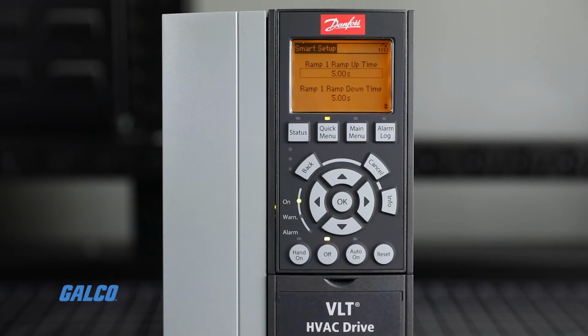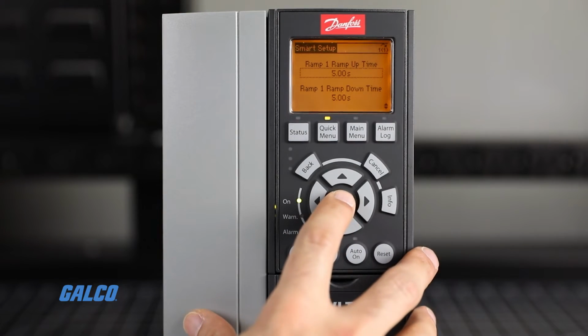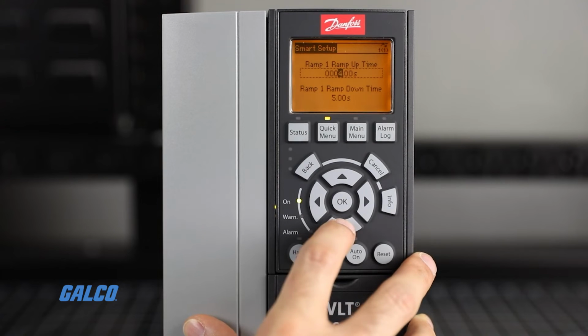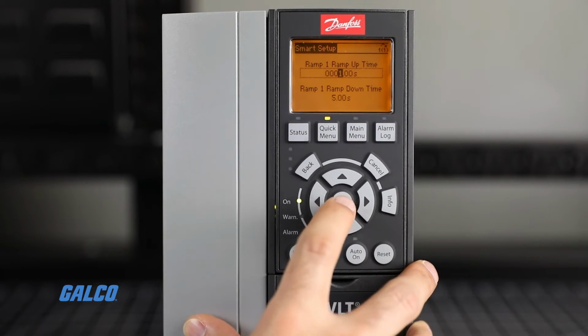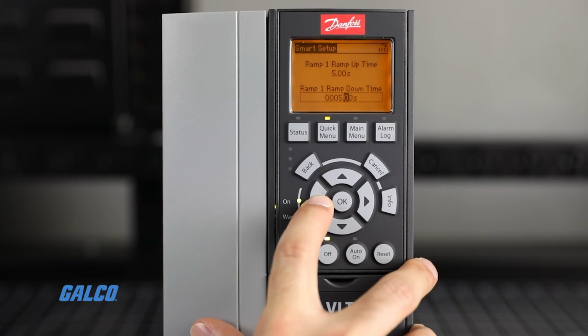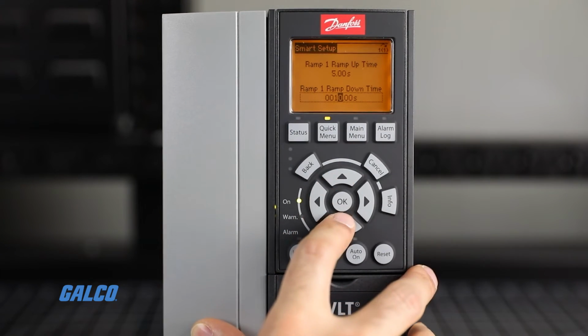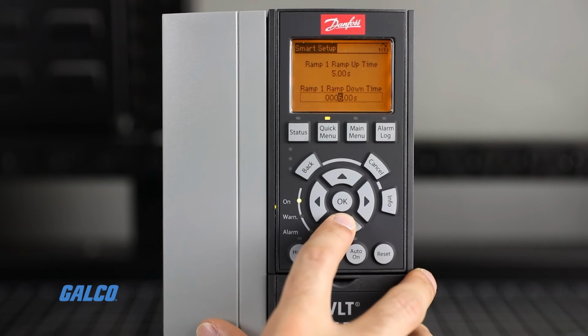The next two parameters, 3-41 and 3-42, set the ramp up and ramp down speed for the motor. They are based on the motor's full speed. If we set 3-41 and 3-42 to 5 seconds, then it will take the motor 5 seconds to reach its max speed and 5 seconds to slow down to a stop.